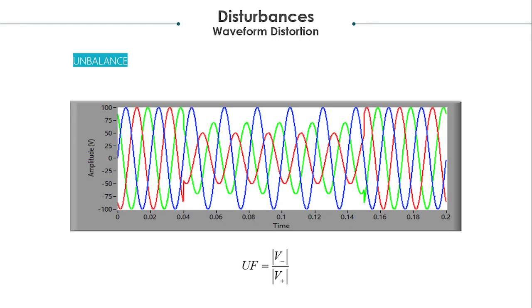The unbalance is also considered a power quality disturbance that occurs when having different RMS magnitudes of the phases or when the phase angle between each consecutive line is not equal, as is clear here between 0.04 seconds and 0.15 seconds. The main reason for unbalance is adding loads on a particular phase more than the others. Therefore, many power quality indices affected by these power quality issues are tackled, including the RMS voltage, the total harmonic distortion, the distortion index, the crest factor, the displacement power factor, and the true power factor. These power quality indices are crucial in representing, quantifying, and comparing complex power quality phenomena.